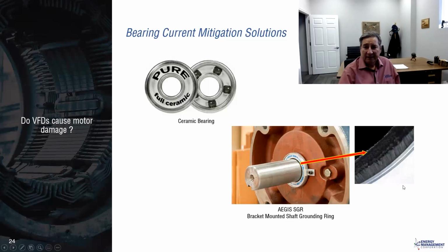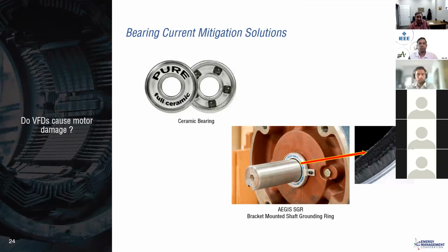Thanks for the question. As I'm just talking now about the output of the drive, we've got the input to talk about also. I'm sure you've heard of taking regular carbon brushes and having them ride on the shaft of the motor. That's what they did certainly in the old days with generators. Now this technology of having fiber strands in a ring that are very robust, as long as you have it in a location where it doesn't get caked with oil and dirt, we typically like to put them inside the motor rather than outside the motor, but you can do either one if you've got an environment for it.